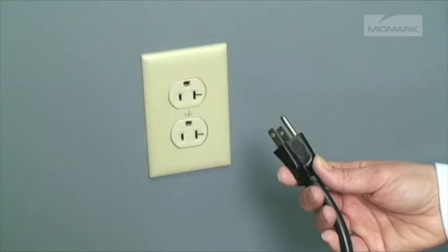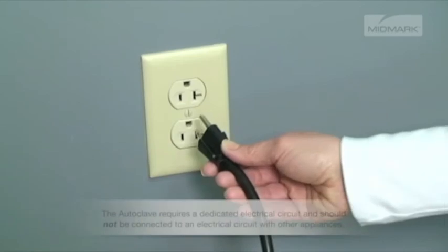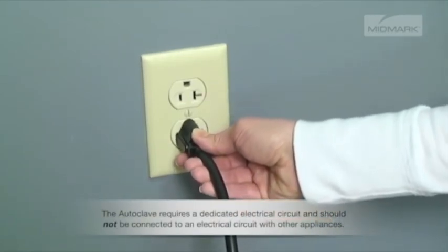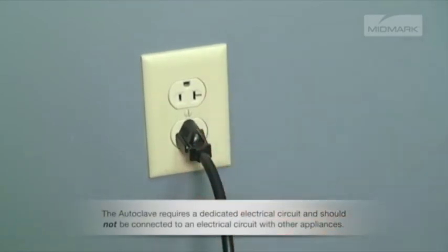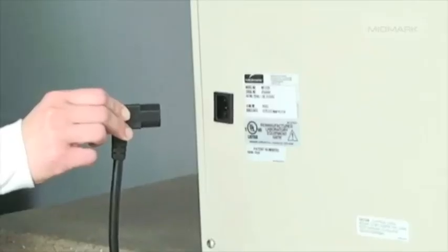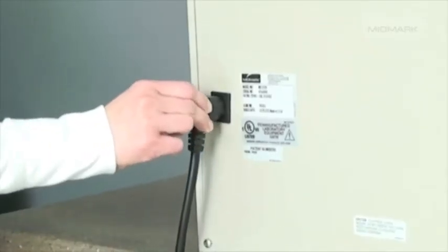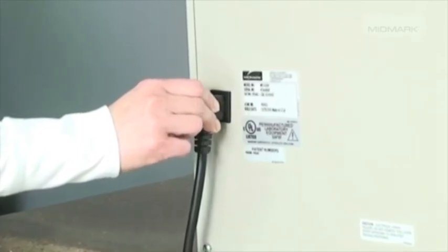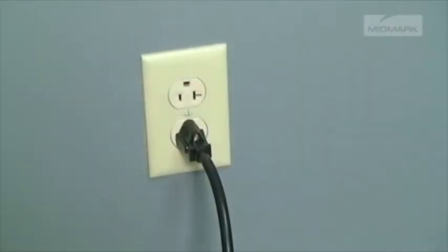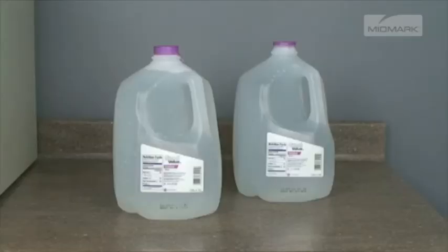In all cases, it is necessary to use a 3-prong grounded circuit. In either voltage configuration, the maximum power consumption is approximately 1500 watts. The autoclave requires a dedicated electrical circuit and should not be connected to an electrical circuit with other appliances. After ensuring proper electrical requirements, attach the electrical cord to the back of the autoclave and then into the wall socket. Now you will want to fill the reservoir with clean, distilled water.